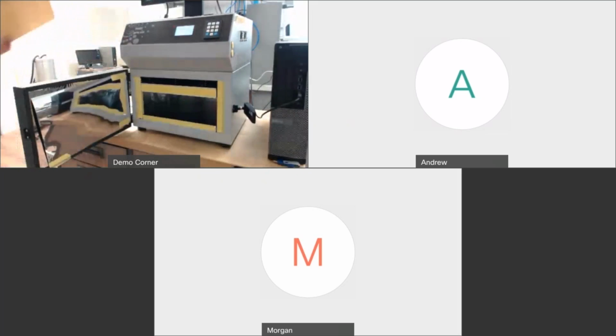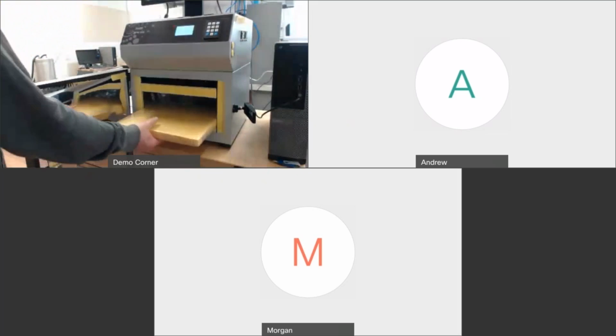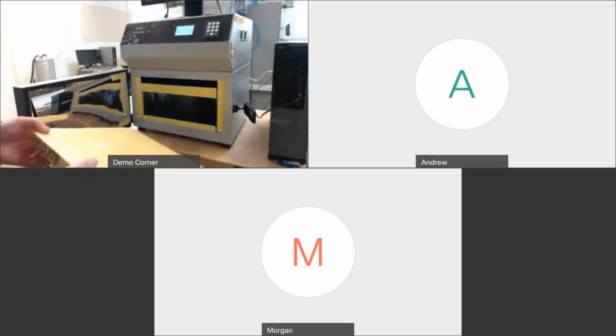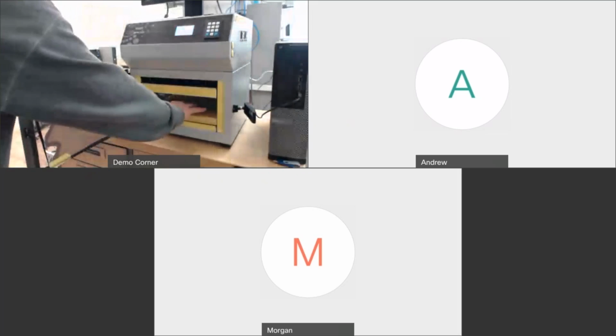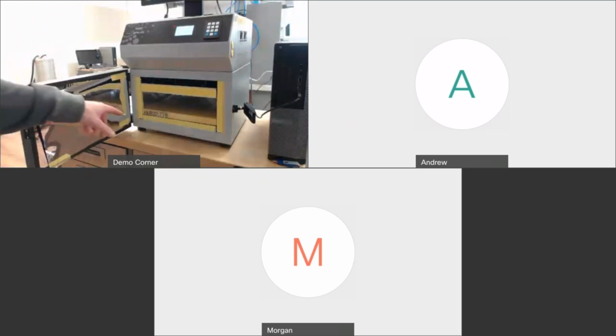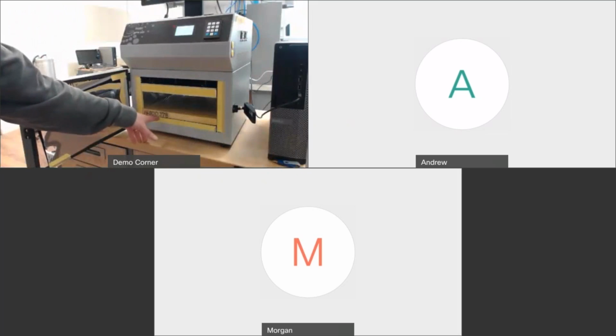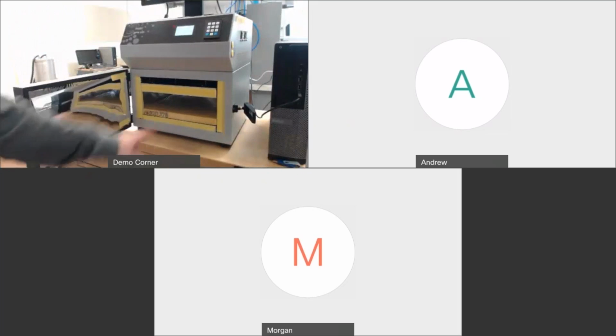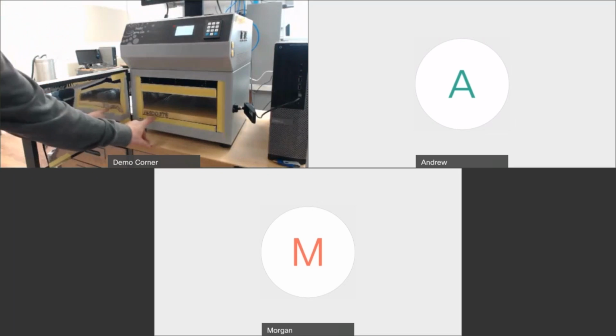Now with this device, yours, you'll want to calibrate. Are you going to run different temperatures, or are you just going to do room temperature essentially? Room temperature. Okay. So yours would be either 1450D or 1450E. This is the NIST fiberboard that comes with it. Value that, and the reason why is that piece of material is about $500. So don't put any books on it. Don't lean on it. Don't spill your coffee on it. Value it. That's the same piece of material that has come with several machines over the past exactly two decades. Yeah, and it only changes in the letter.